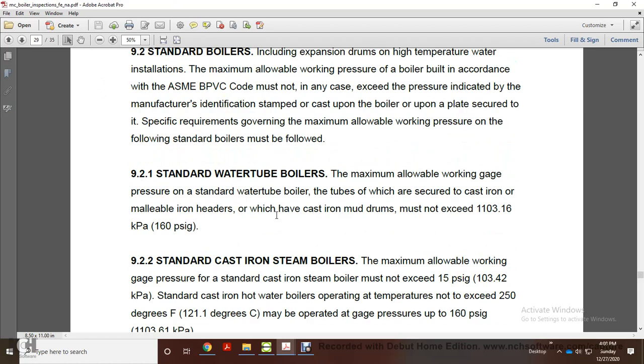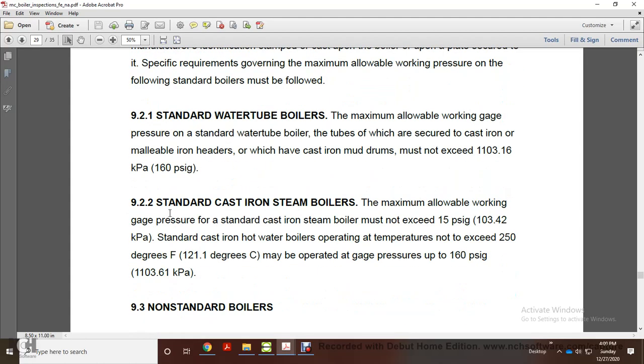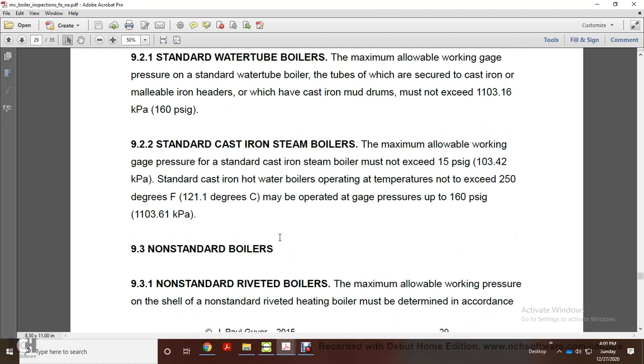9.2.1 Standard water tube boilers. The maximum working gauge pressure for a standard water tube boiler with tubes secured to cast iron or malleable iron headers, or which has cast iron mud drums, must not exceed 1103.16 kilopascals. 9.2.2 Standard cast iron steam boilers. The maximum allowable working gauge pressure must not exceed 15 psi gauge. Cast iron hot water boilers with operating temperatures not exceeding 250 degrees Fahrenheit may be operated at a gauge pressure up to 160 psi gauge.